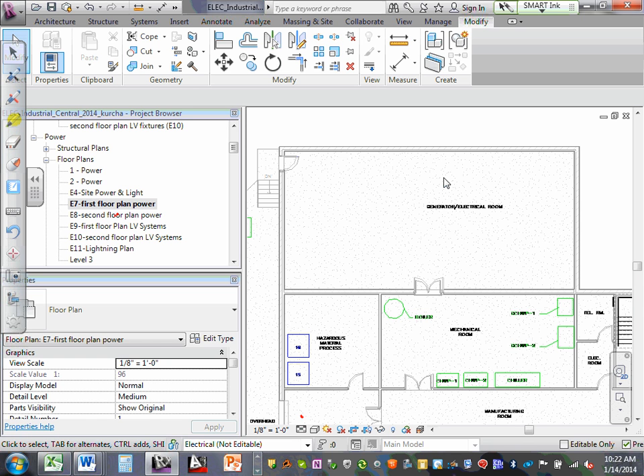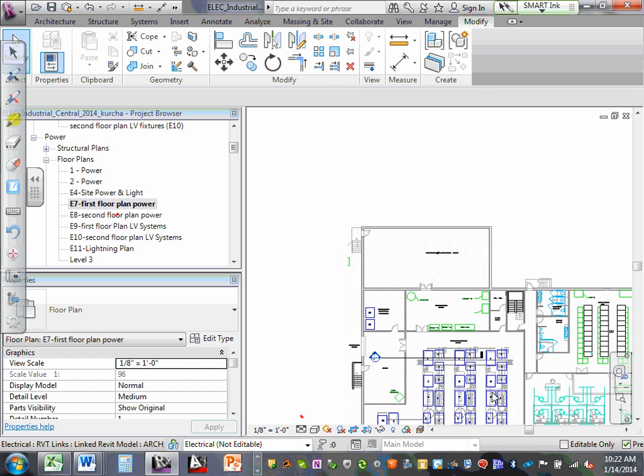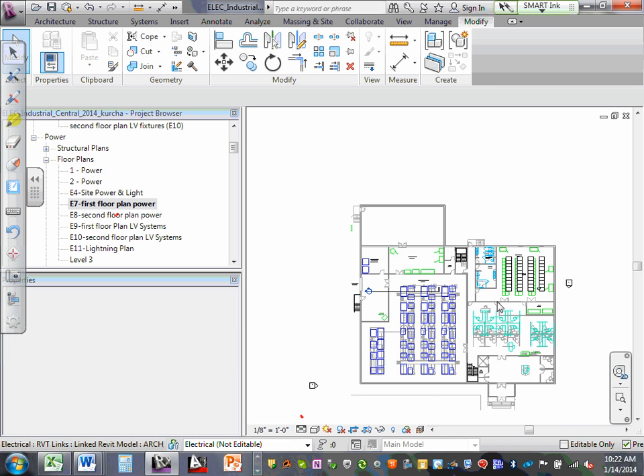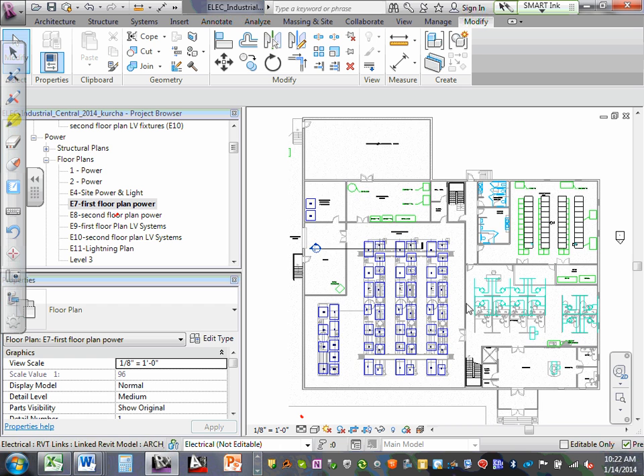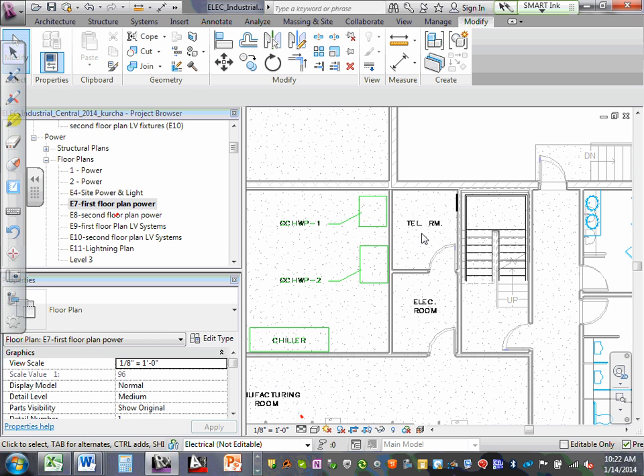So, the fire alarm system, I guess we should talk a little bit about just the basics of the fire alarm system. You've got a control panel, you've got detection devices, you've got notification devices. Pretty much talked about all the detection and notification devices at this point. The control panel itself, there are two basic technologies. One is known as conventional, the other is known as addressable. I don't believe anybody should be designing a conventional system anymore. The technology in our industry is essentially 100% addressable technology.